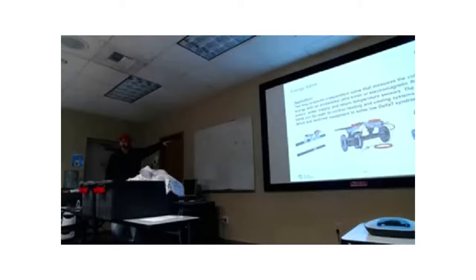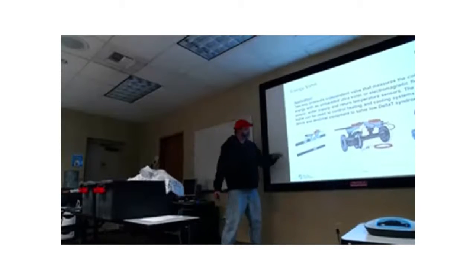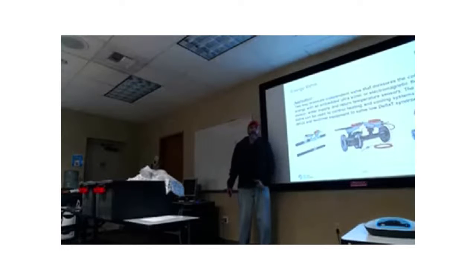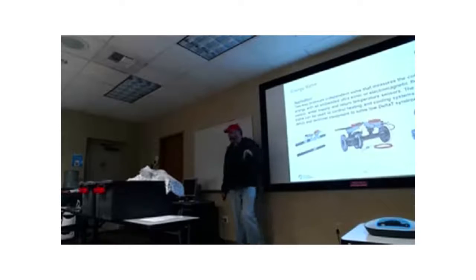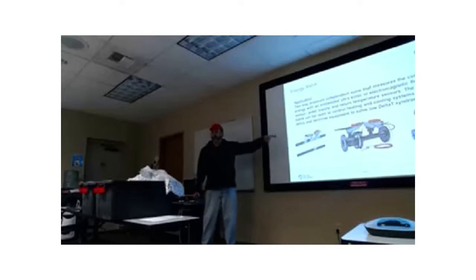That's not good. Why? You're less efficient, right? Just like you said, you're less efficient. What you want to do for any coil that's out there, you want to give it just enough water so it gets the heat transfer rate you want, and you want to maximize that delta T. You want to make that delta T as big as you can get for any given point in the coil. So what this valve does in a nutshell, it's not only like a control valve and a BTU meter, it's actually a device that takes that data. It actually measures the flow rate, it measures the temperature, and it stores it right on the valve.